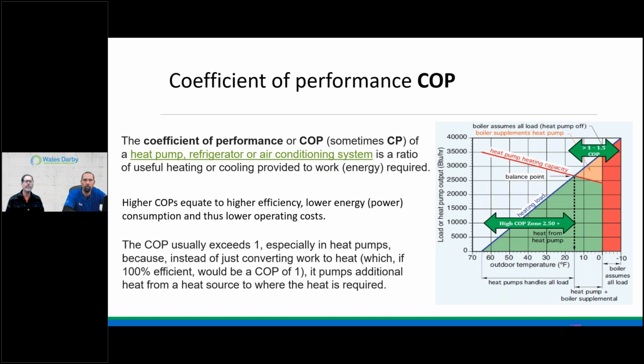All right. So you can see this chart, a lot of lines going left and right, but it's showing you basically in the green, that's the heat pump. That's where we're achieving those high efficiencies. As we go left to right on the bottom, that's outdoor temperature. So at 20 degrees and going up, this piece of equipment is still producing almost 25,000 BTUs. Now, if you never do a heat loss or understand what a house requires, that's a good chunk of most people's homes. Right.